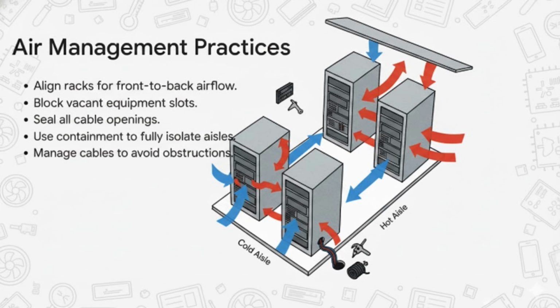But to make that layout really work, you have to be obsessive about the details. Every single little gap allows air to mix and waste energy. That means using blanking panels to cover empty slots, sealing up every cable opening, and even using containment systems, like plastic curtains or doors, to completely isolate the aisles from each other. Even messy cables can create hotspots.